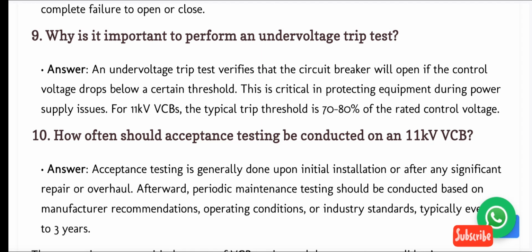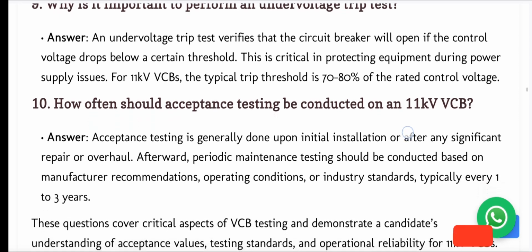9. Why is it important to perform an undervoltage trip test? Answer. An undervoltage trip test verifies that the circuit breaker will open if the control voltage drops below a certain threshold. This is critical in protecting equipment during power supply issues. For 11 kV VCBs, the typical trip threshold is 70–80% of the rated control voltage.